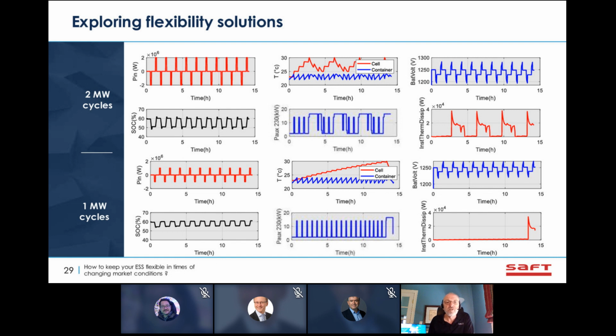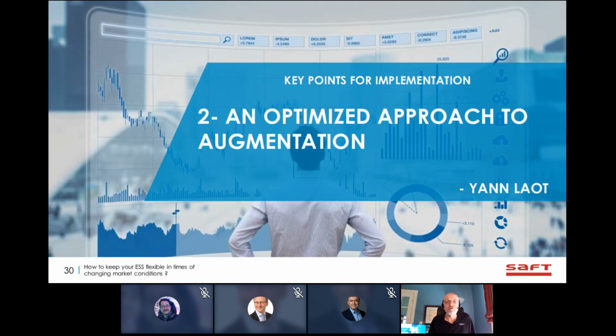Looking at the center pair of charts in each set: the upper one shows the temperature profile for the cells and the ambient container temperature, and the lower chart shows the operation of the HVAC and fans. When we switch to 2 megawatts of operation, we're having to operate the thermal management system much more aggressively. There's nothing special about that conclusion, but here we have the ability to quantify what that means in auxiliary power consumption. That's my part of the presentation, and I'll hand off now to Jan.